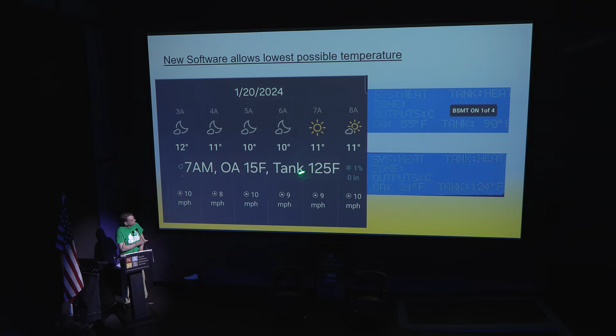this heating season, we were able to install a software upgrade to the air-to-water heat pump, which does a better job of looking at outdoor temperature and saying, well, how much heat needs to go into that white tank to make all the rooms comfortable? So if it's 15 degrees outside, the tank needs to be 125, and I think that pretty much proves some of the HVAC contractors that say, well, you just can't do that with old water radiators. Well, yes, we can. So here's on the heat pump itself. You can see that when it's 24 degrees outside, the tank needs to be at 124, but when it's warmer, when it's 55, the tank only needs to be at, that looks like 90 to me from this angle.